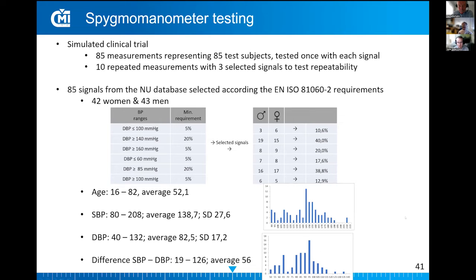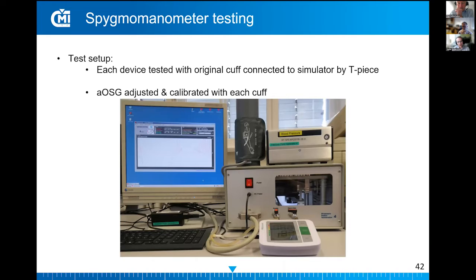On the right side, you can see the distribution of blood pressures we tested the devices with, and all these parameters fulfill the requirements of this European standard 81060-2. The measuring setup was something like this. Each device was tested with its original cuff connected to the simulator, the aOSG, by T-pieces. Prior to each test, we adjusted and calibrated the simulator with each cuff, so we would minimize the internal volume influences.